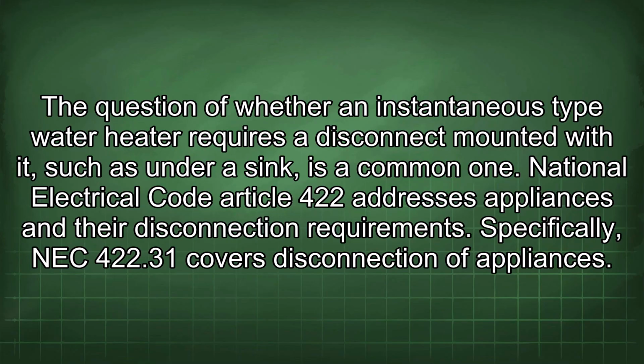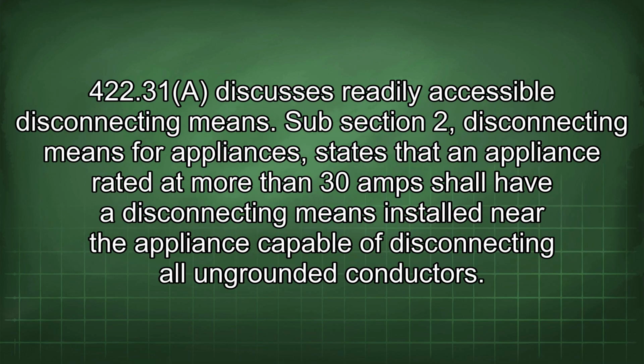The question of whether an instantaneous type water heater requires a disconnect mounted with it, such as under a sink, is a common one. National Electrical Code Article 422 addresses appliances and their disconnection requirements. Specifically, NEC 422.31 covers disconnection of appliances. 422.31 discusses readily accessible disconnecting means.